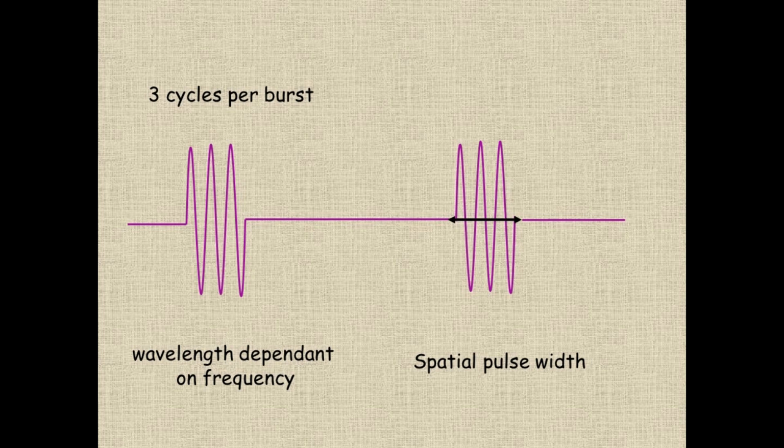Ultrasound waves are generated not as continuous bursts of energy, but as cycles of energy, typically in very short bursts, around 3 cycles per burst. So there'll be 3 or 4 wavelengths sent out. There'll be a big delay before a similar packet is repeated. During the delay, that gives enough time for the sound to enter the tissues and be reflected back, which means that with each burst of energy, the ultrasound machine then listens to see what's coming back.